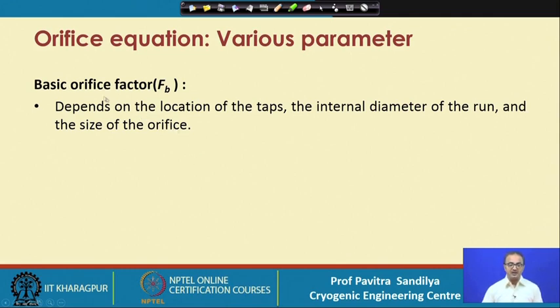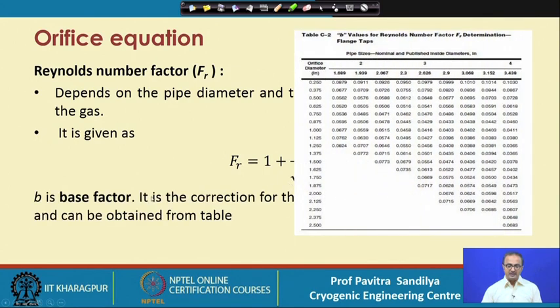The basic orifice factor depends on the location of the taps, the internal pipe diameter, and the size of the orifice, and is obtained from tables in the literature. The Reynolds number correction factor depends on pipe diameter, viscosity, density, and gas velocity, and is given by a particular expression where B is a base factor also obtained from tables in the literature.